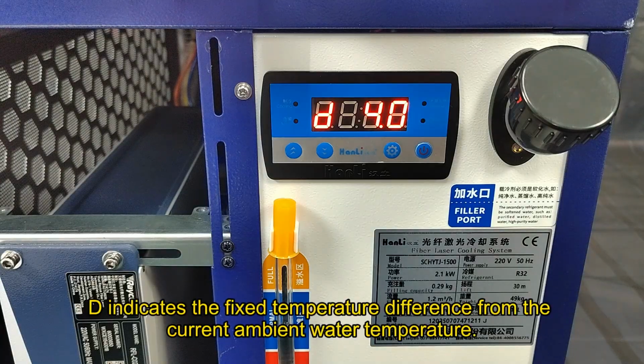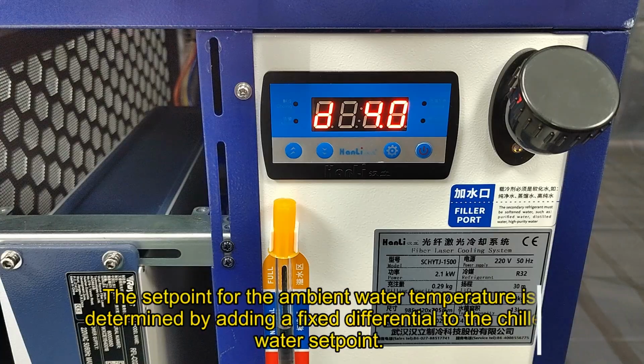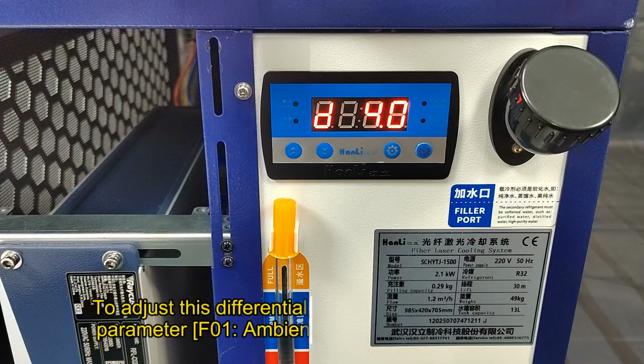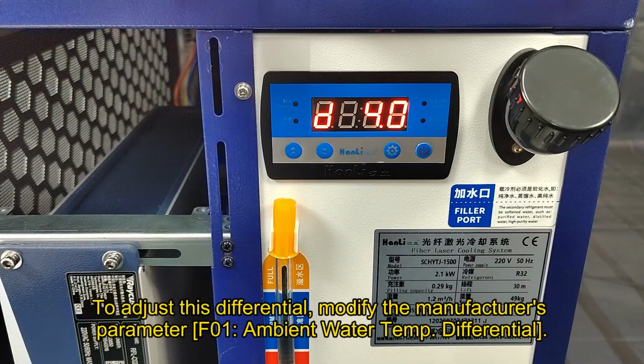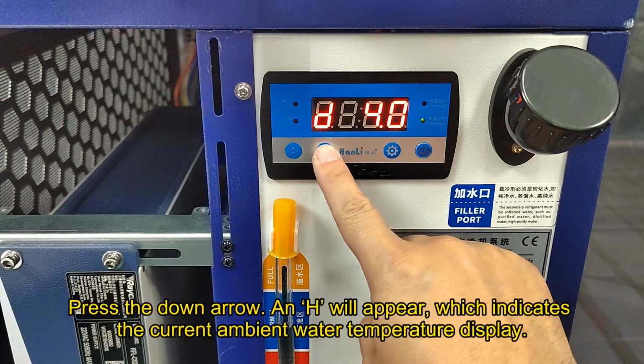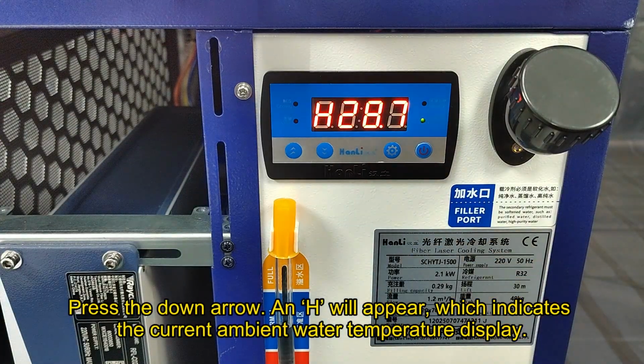D indicates the fixed temperature difference from the current ambient water temperature. The set point for the ambient water temperature is determined by adding a fixed differential to the chilled water set point. To adjust this differential, modify the manufacturer's parameter F01, ambient water temp differential. Press the down arrow, and H will appear, which indicates the current ambient water temperature display.